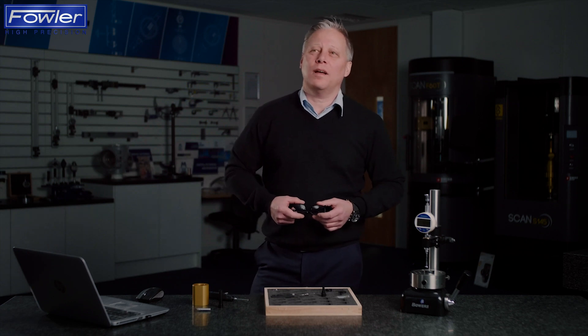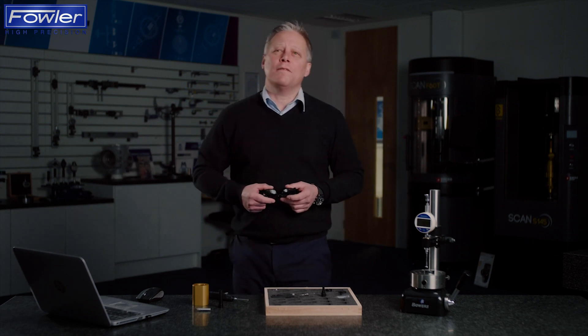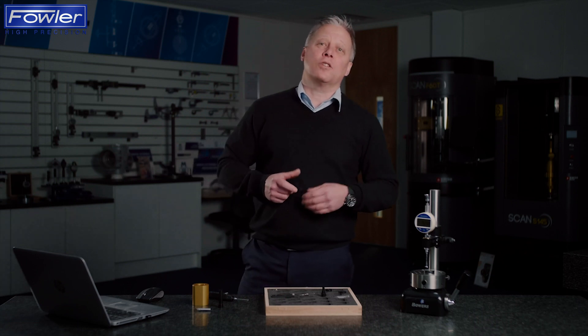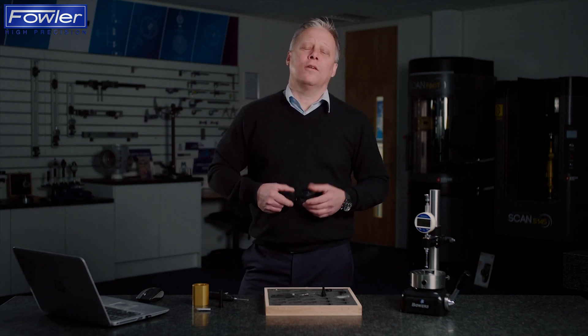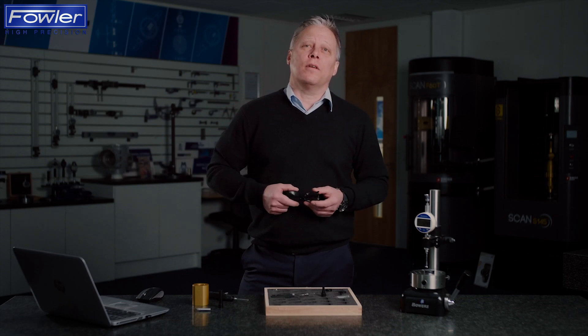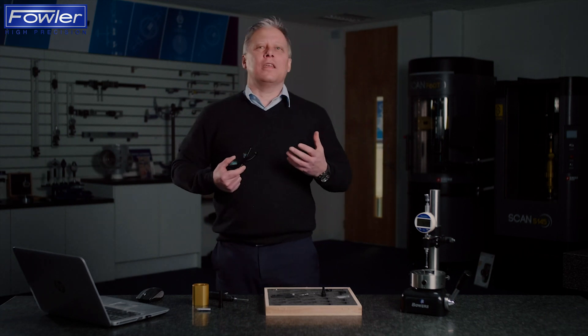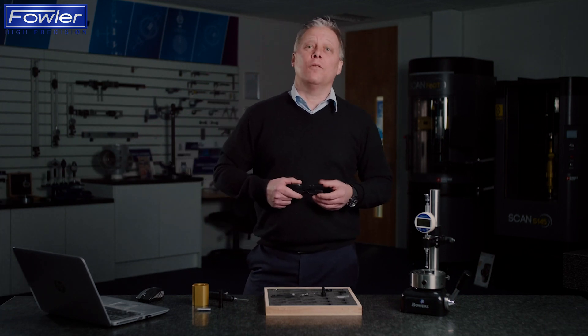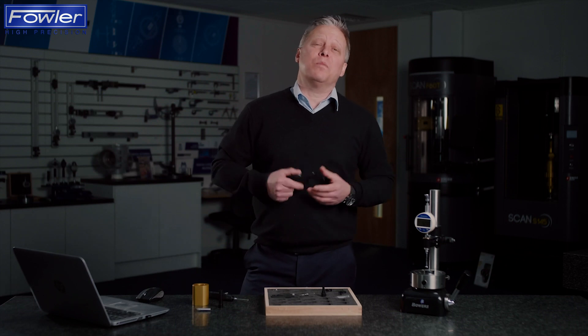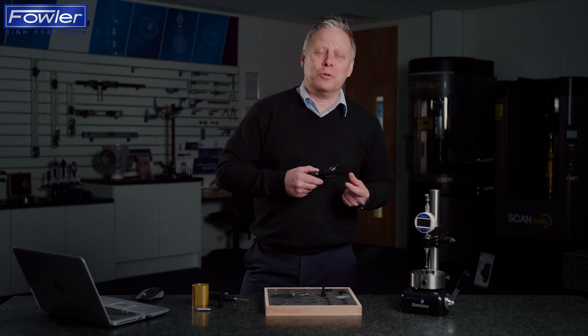Hello and welcome to this product update from Fowler. Many of you will be aware of the difficulties in measuring small diameters, often reverting to the use of pin gauges to try and check whether this small diameter is within tolerance. Obviously this doesn't tell us anything about the form of that diameter or indeed its size, simply that it's at least as big as the size of the pin we were able to push into it.